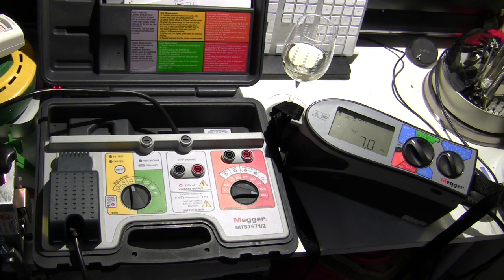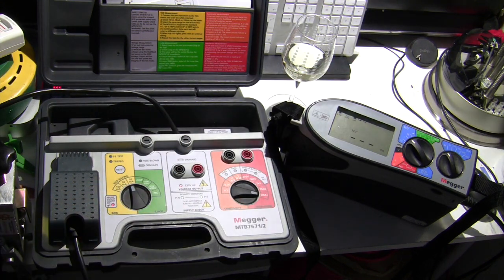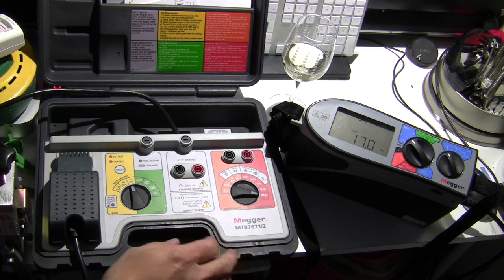Reset that, and again I'm going to switch that to 180 degrees, and the numbers change again. Instead of it reacting within 10 milliseconds, it goes up to 20 milliseconds. So let's press the test button and we should see a result below 20. 17.0. Super. So that's all good.